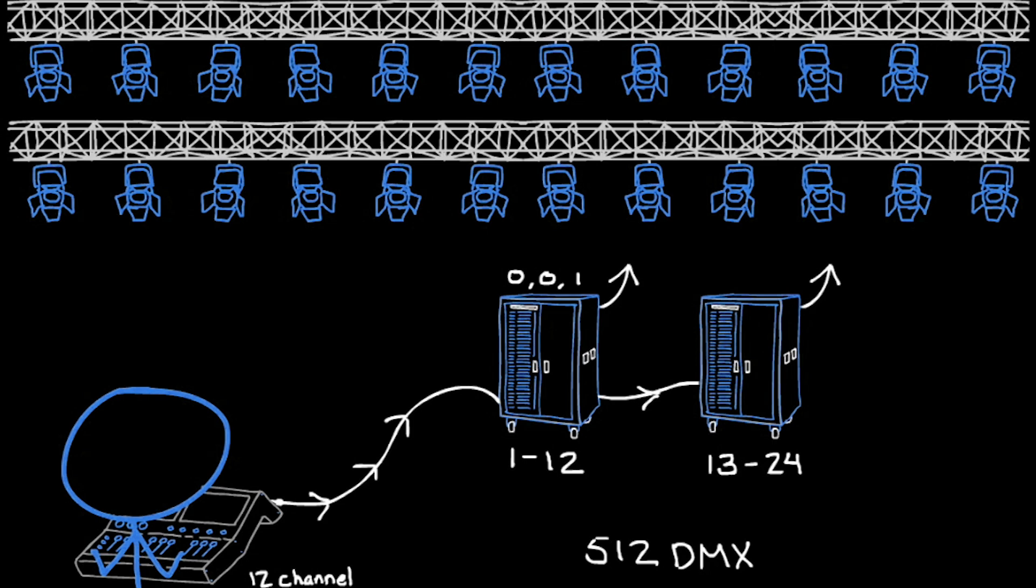We only have a 12-channel console because they couldn't afford a 24-channel console to talk to all 24 dimmers. They have 24 lamps, 24 dimmers, and a 12-channel console, which one would think is a problem, but it isn't. DMX can make this dimmer exactly the same as that one by addressing it to 001. Therefore, it mimics this dimmer here.